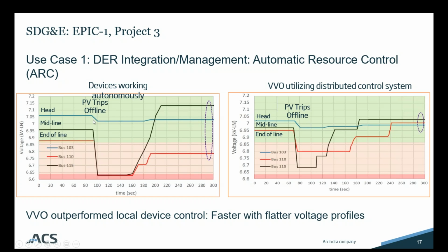Next thing that you can take away from the first case scenario is when the PV trips offline, there is 60 seconds before the midline and end of line voltages start to recover. Now that's a direct correlation to how those controls are actually set up. So clearly there is a large time delay before those controls start reacting. And then the third takeaway from devices working autonomously by themselves is, even when they return to a steady state, you can see that there's still a tremendous voltage gap and a large delta voltage between the head and midline voltages and the end of line. Also, the red indicates various voltage violations. The lighter red shows an area where temporary voltage violations can occur, and the darker red is voltage levels that should not be penetrated.